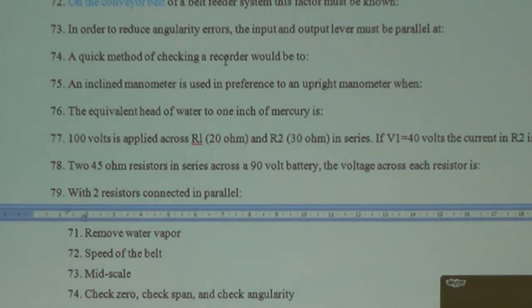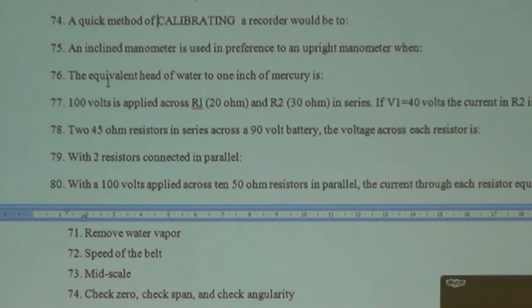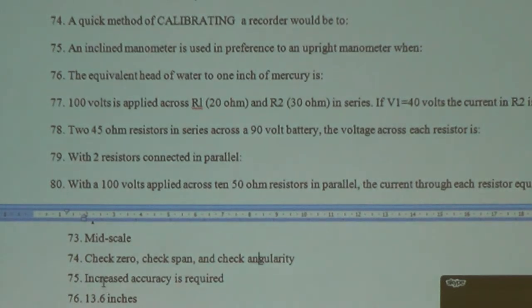A quick method for calibrating - instead of checking, just use this word calibrating. So you do a zero check, a span check, and an angularity check. Inclined manometer is used in preference to an upright manometer whenever you need to have increased accuracy.